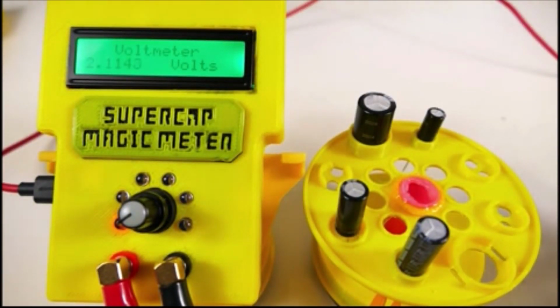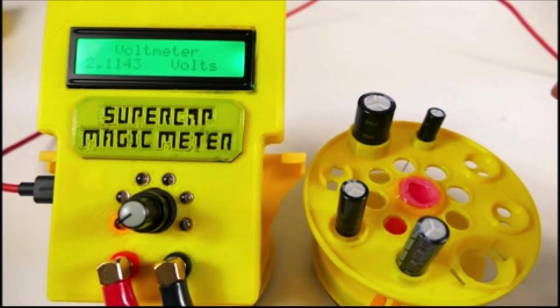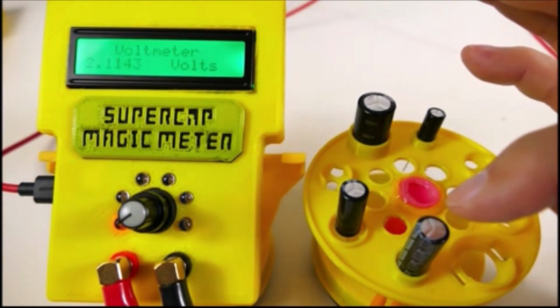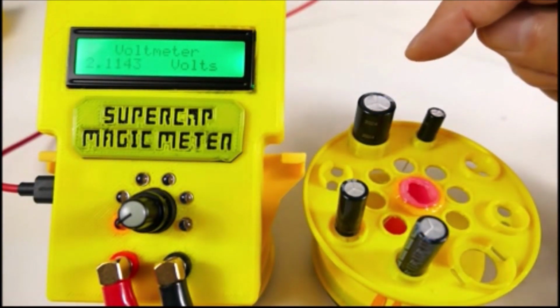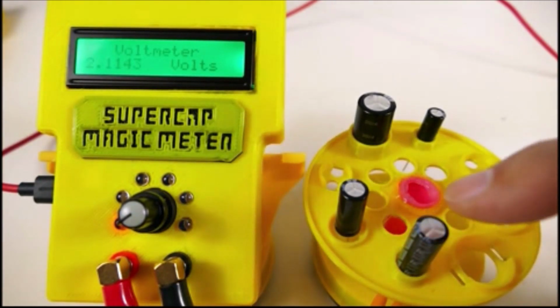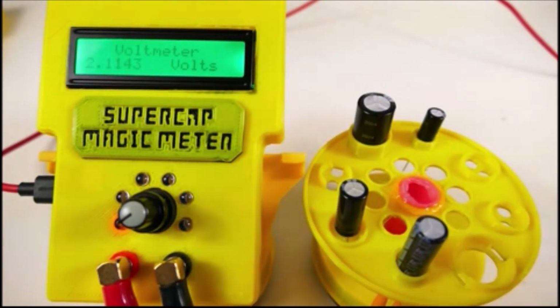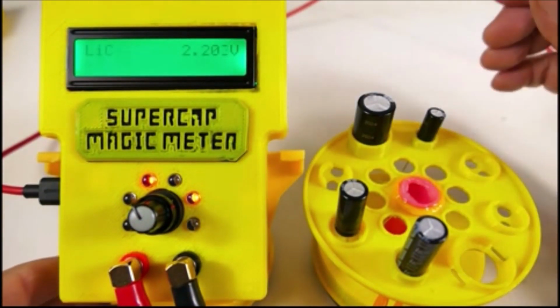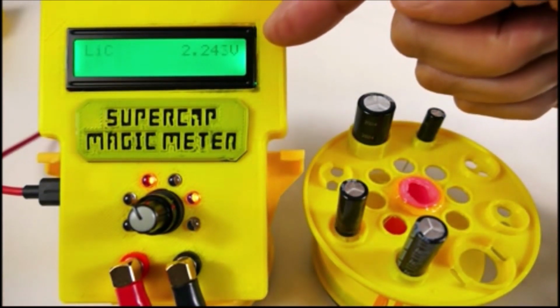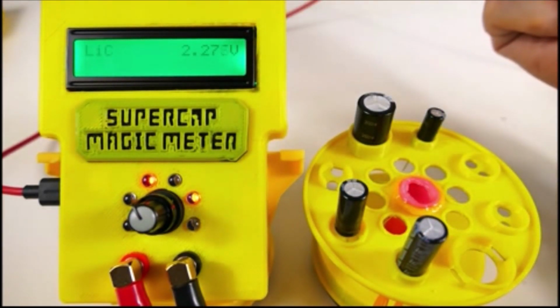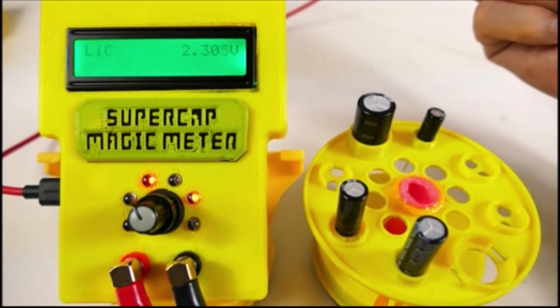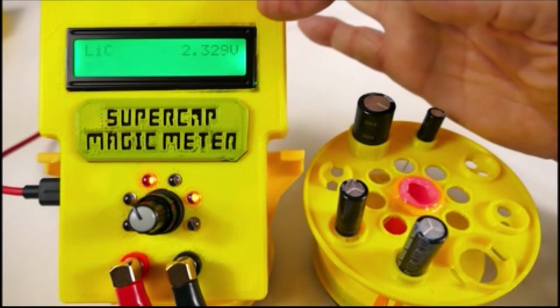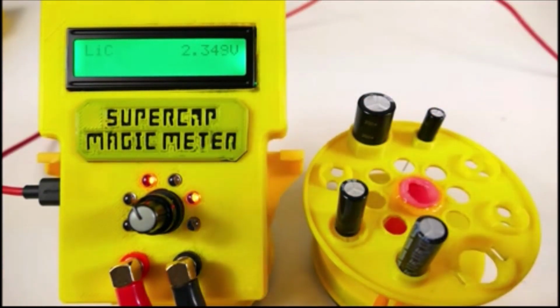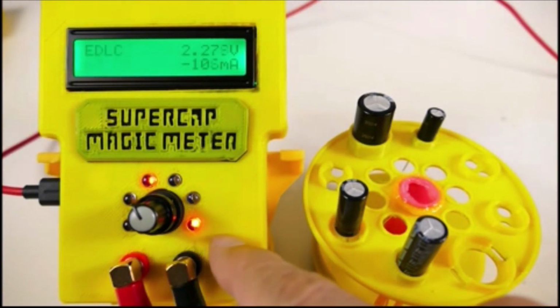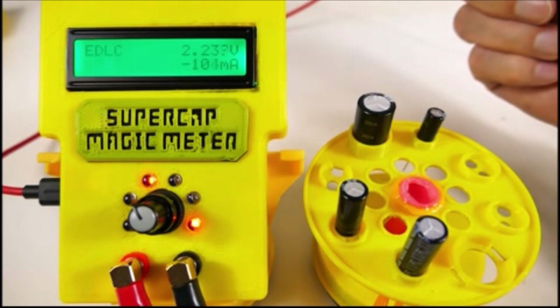Alright, I'm going to demonstrate this SuperCap magic meter measuring some capacitors. This one is 10 farads, 7 farads, 25 farads, and 3 farads. Right now it's connected to the 10 farad capacitor and it's just measuring the voltage. So if I switch it to measure capacitance, it's charging up to 2.35 volts to get started with the measurement. And I've just displayed the voltage so that you can see what's happening. You can see that it's charging there, and then here you can see it's discharging, and the current is 104 milliamps.